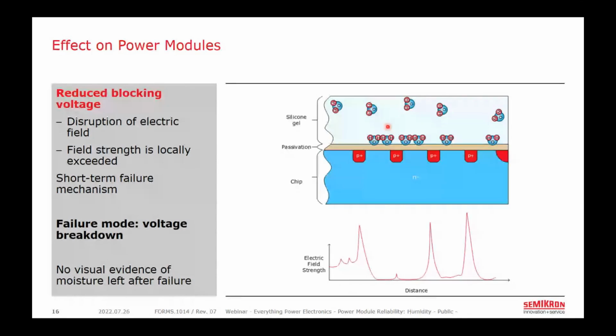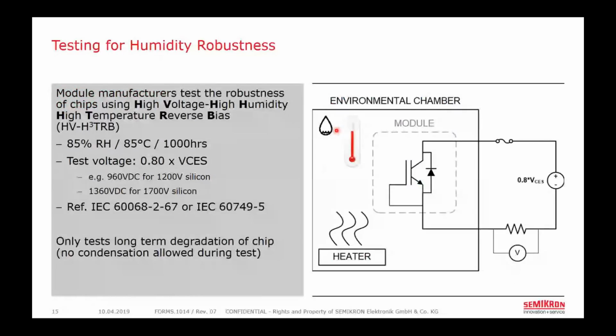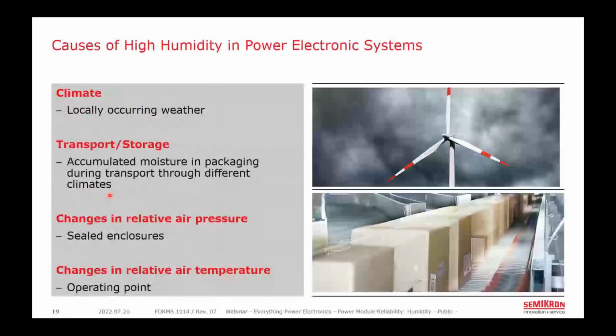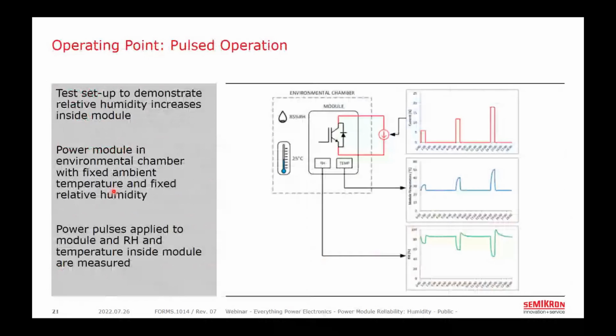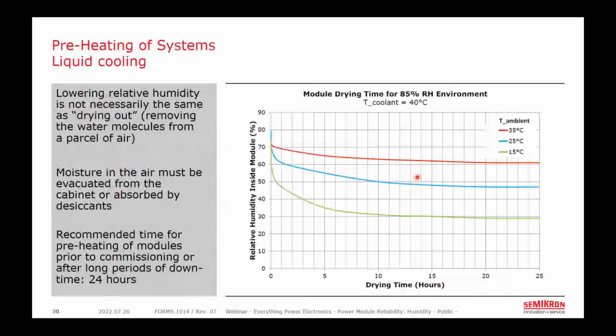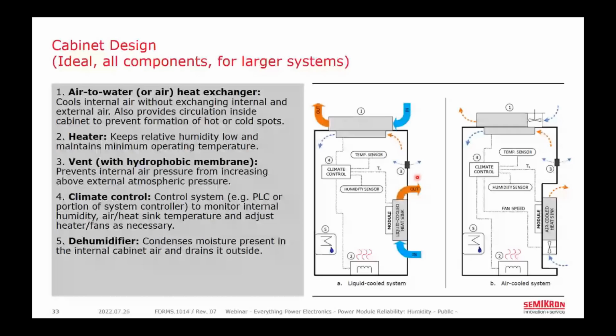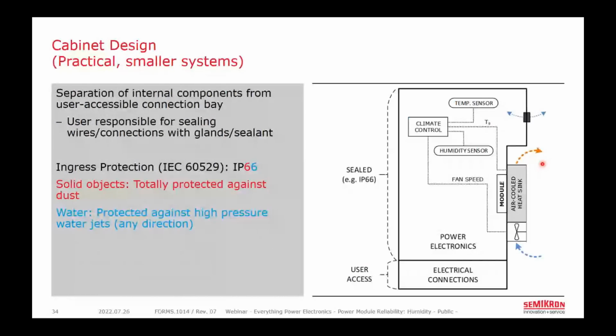One is making sure that you're getting modules from a power semiconductor manufacturer that have passed so-called HV-H3TRB. So some of the testing is done by the module manufacturer. Some of our customers will repeat this testing on their system. Ideally, if it's feasible, what we'd like to see is a finished system or cabinet. So let me go to a picture. A system like this. Ideally, we would like to see this finished unit put into an environment like defined by the IEC standard, and then run and tested.